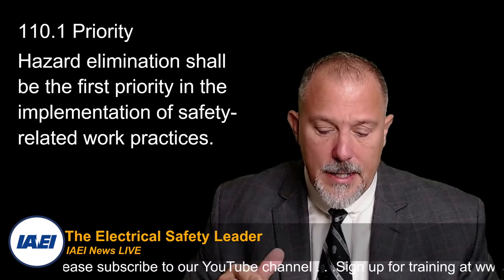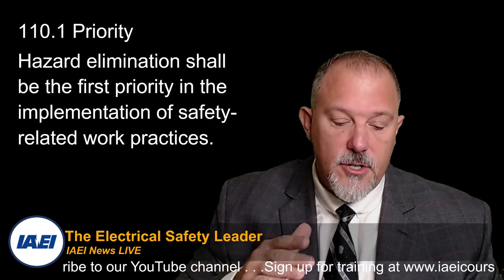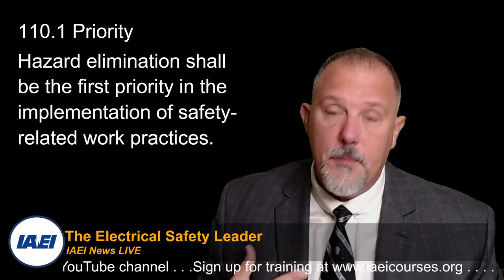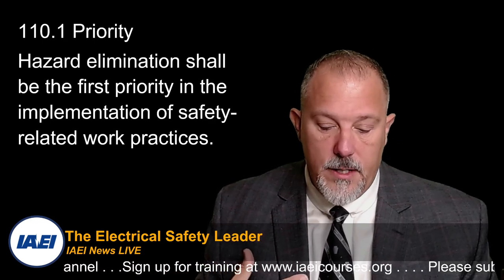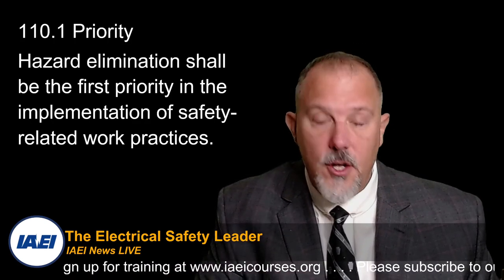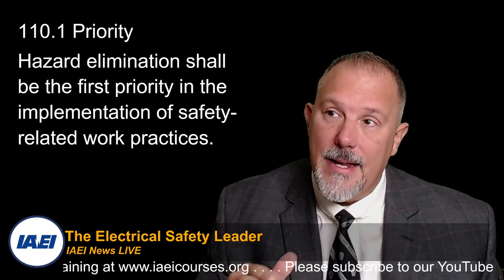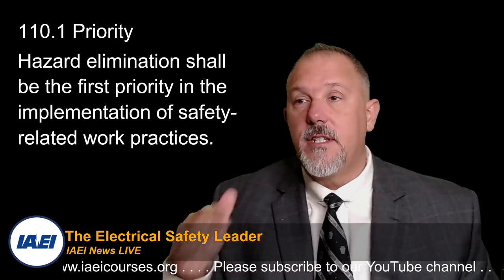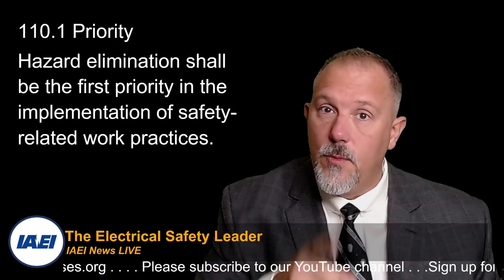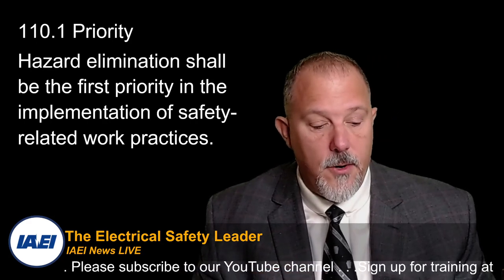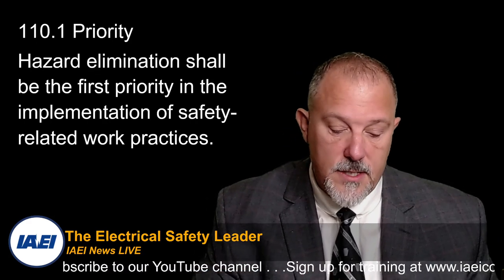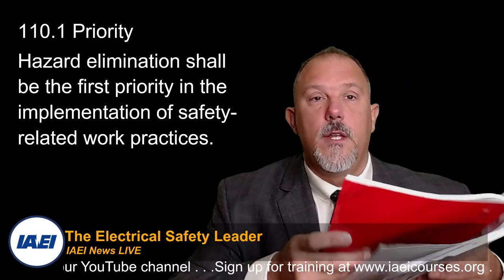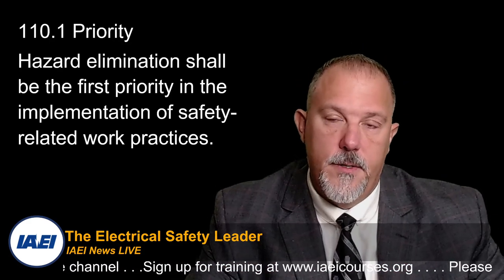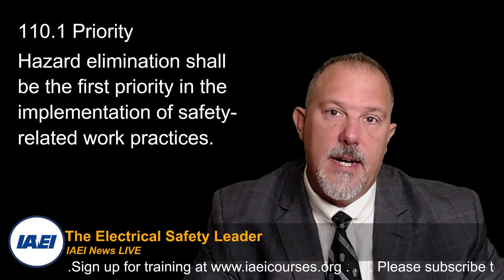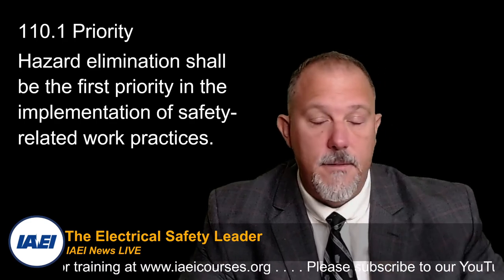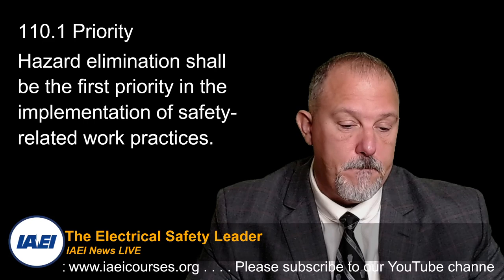So it's important to understand, and I tell design engineers this, and I approach things myself from a safety by design perspective, with those two thoughts in mind: likelihood and severity. If the severity is high and I can reduce the likelihood, and we'll talk about some scenarios in that regard in a power distribution system, if I can reduce the likelihood, but the severity is high, by making a design change, I have increased electrical safety.